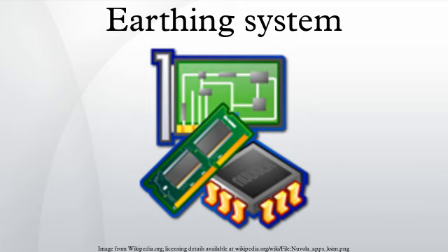TT network: in a TT earthing system, the protective earth connection for the consumer is provided by a local earth electrode, and there is another independently installed at the generator. There is no earth wire between the two. The fault impedance is higher, and unless the electrode impedance is very low indeed, a TT installation should always have an RCD as its first isolator.